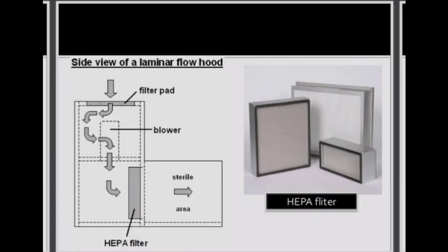The fan sucks the air through the filter pad where the dust is trapped. After that, the pre-filtered air has to pass through the HEPA filter. The full form of HEPA is high efficiency particulate air filter, where the contaminated particles are removed. And lastly, the sterile air flows into the working area.